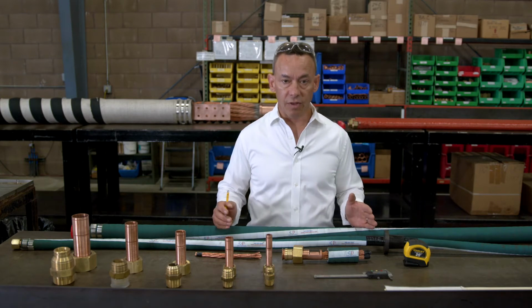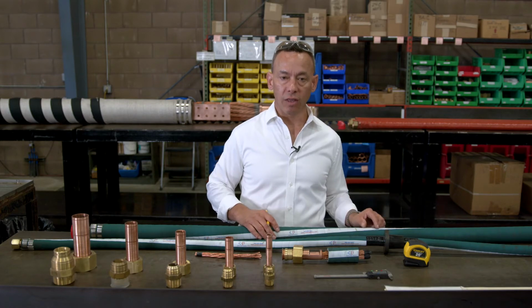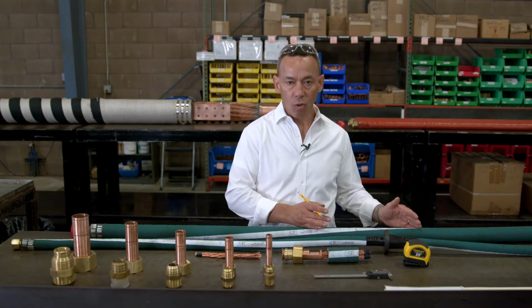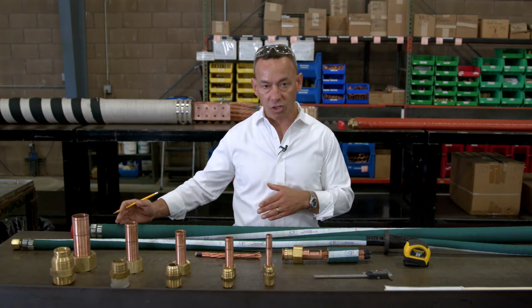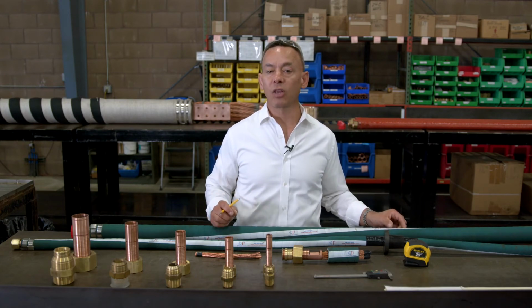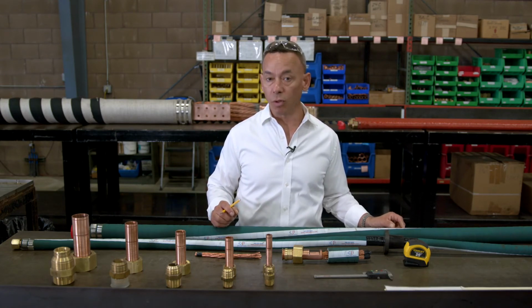The vacuum folks out there, they also have to be able to specify where on the cable they want to locate their vacuum grommet. And that is denoted by the P length. And P stands for power supply. So that P length is telling me how much of the cable is going to be on the outside or the atmosphere of the chamber and connected to the power supply. The V length, which arguably is more critical, is how much of that cable is inside the chamber connecting to your induction melt coil. And so that P length tells me exactly where I need to put your vacuum grommet when I build your cable.